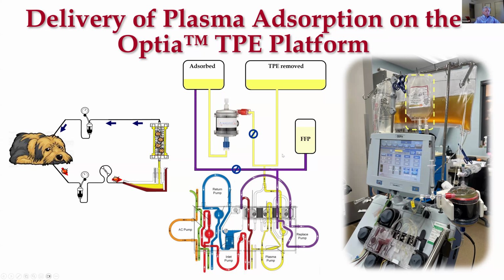After the plasma exchange, we clamp off the line to the bag, and we add in the carbon device on a secondary line that's available on the circuit. These bags only hold 5 liters, so if you needed to remove more plasma, you can attach another bag to this line. But we use that bag to provide plasma to the inlet of the adsorber, and then the outlet of the adsorber goes to a little transition bag.